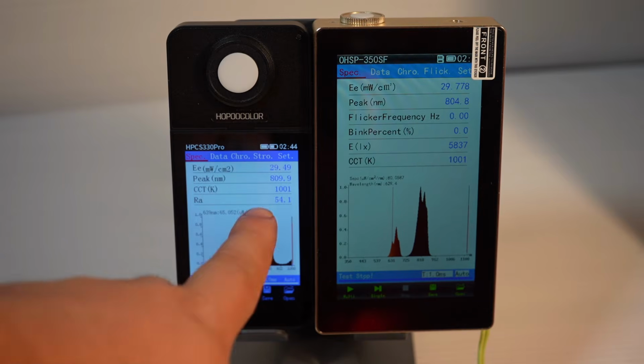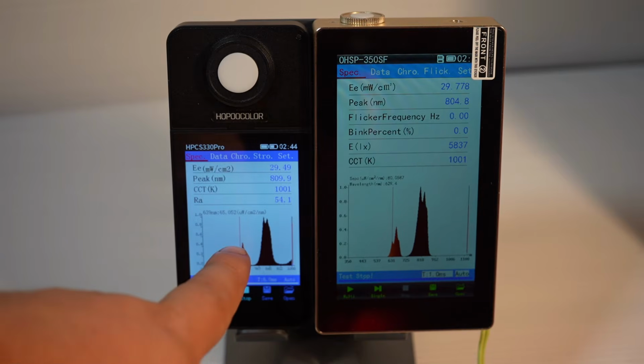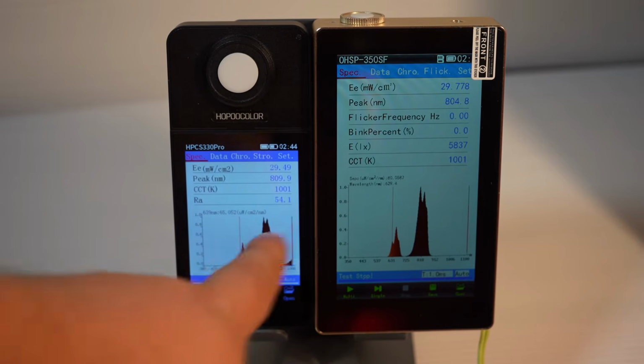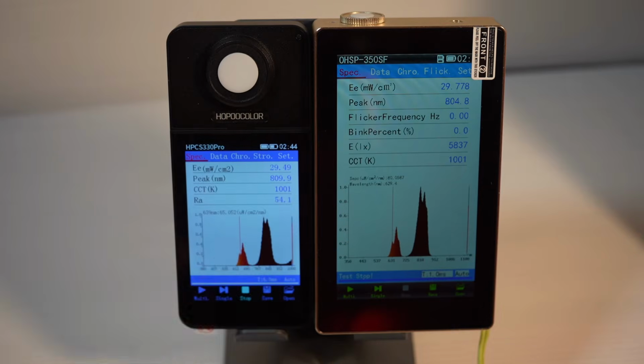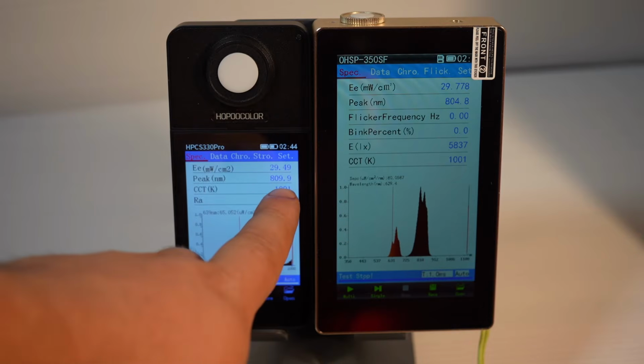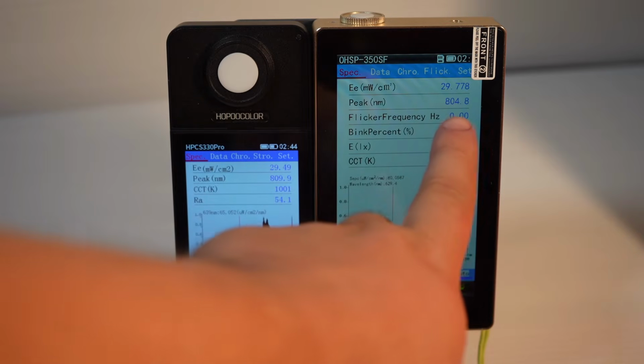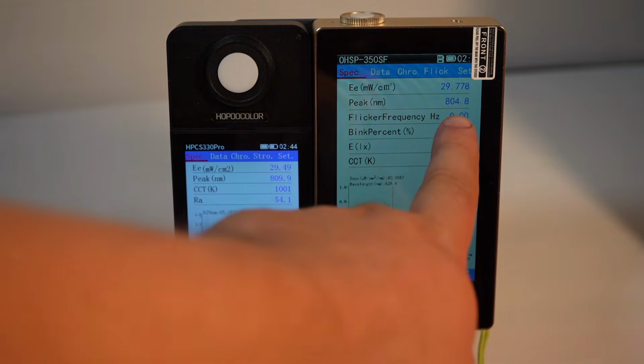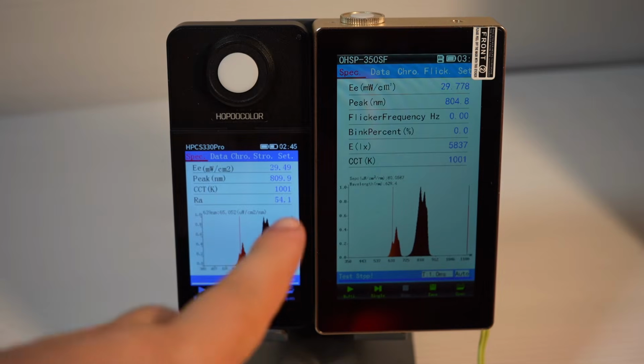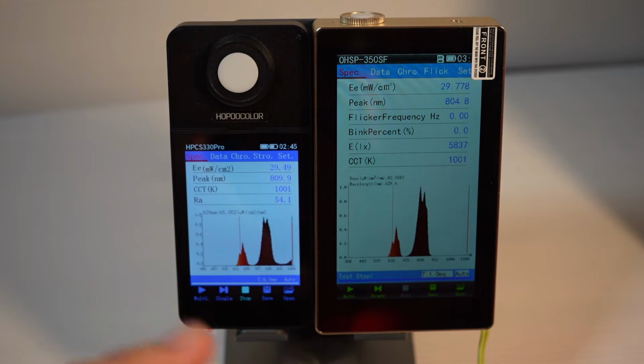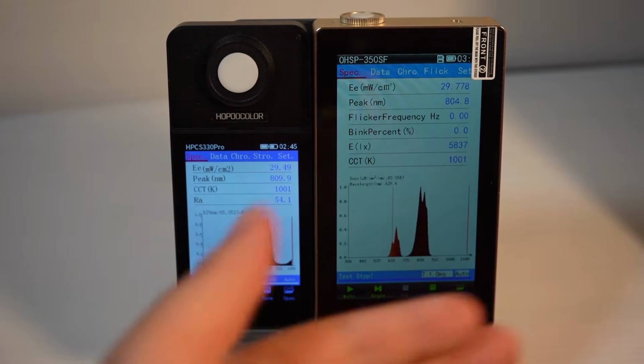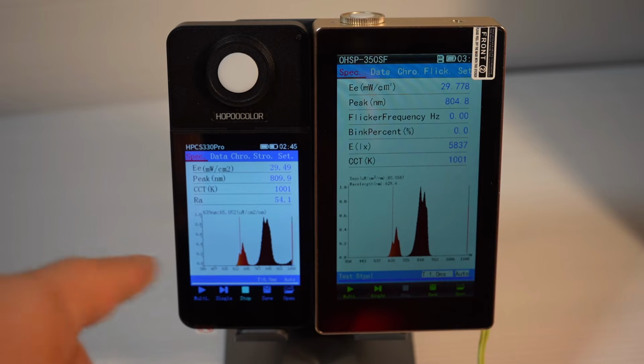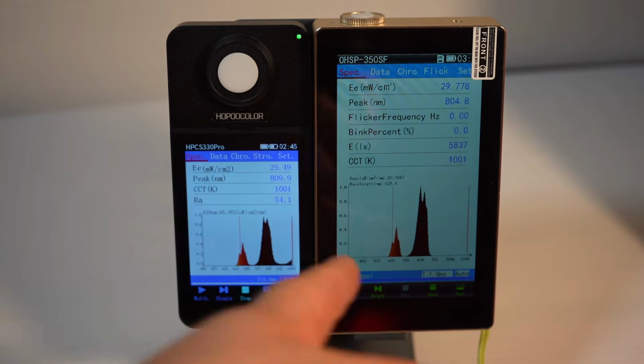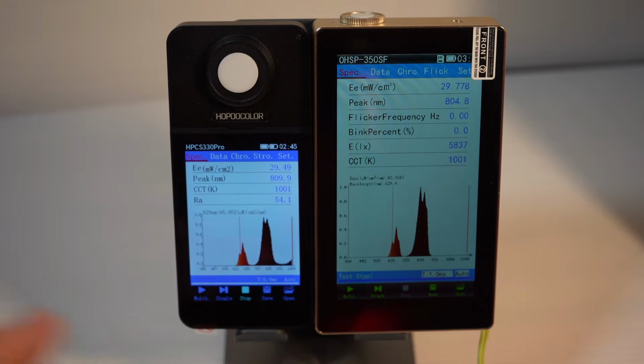But I did notice that the nanometer peak on the cheaper one is about 3 to 4 nanometers higher than the more expensive one. For this one, it's reading 809.9, but on the more expensive one, it's reading 804.8. But we don't know for sure which one is actually more accurate than the other. This one's a little bit older, so there could be some calibration drift over time. This one's a little bit newer, so it's got a fresher calibration. So it could be either one. We can't assume the more expensive one is always more accurate.